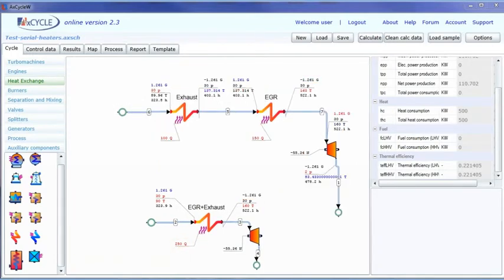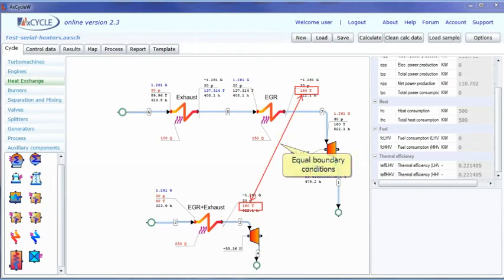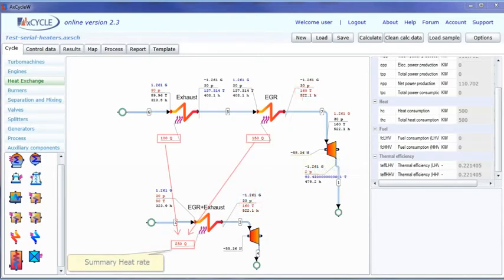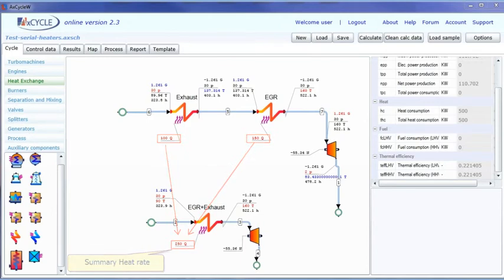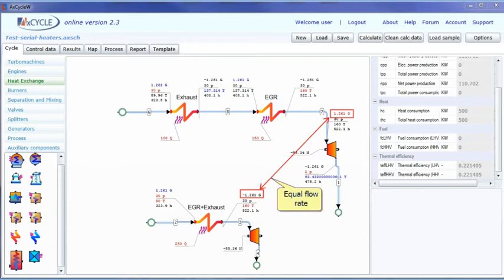In the case of serial configuration, fixed boundary conditions are used for temperature upstream and downstream the series of heat sources. Mass flow rate through each is calculated, with a total mass flow rate of 1.261 kilograms per second — exactly the same as for one heater with equivalent heat rate. This small study shows that either parallel or serial heat sources may be correctly replaced with a single source using the summary heat rate.